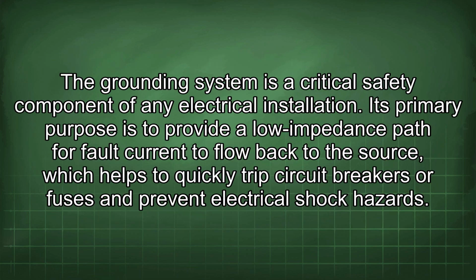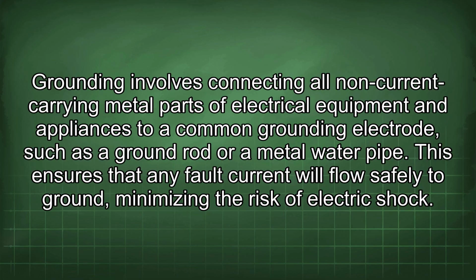The grounding system is a critical safety component of any electrical installation. Its primary purpose is to provide a low impedance path for fault current to flow back to the source, which helps to quickly trip circuit breakers or fuses and prevent electrical shock hazards. Grounding involves connecting all non-current carrying metal parts of electrical equipment and appliances to a common grounding electrode, such as a ground rod or a metal water pipe. This ensures that any fault current will flow safely to ground, minimizing the risk of electric shock.